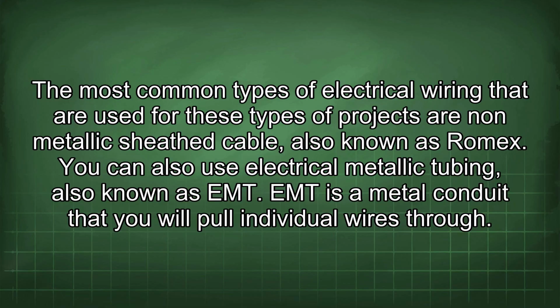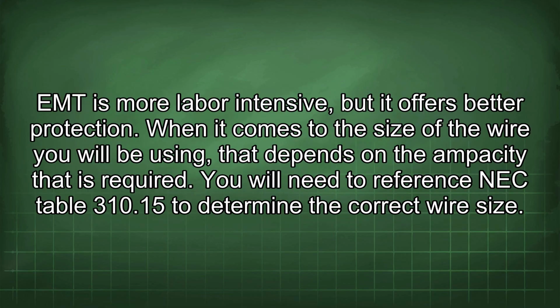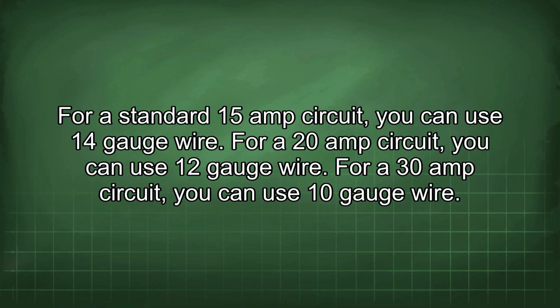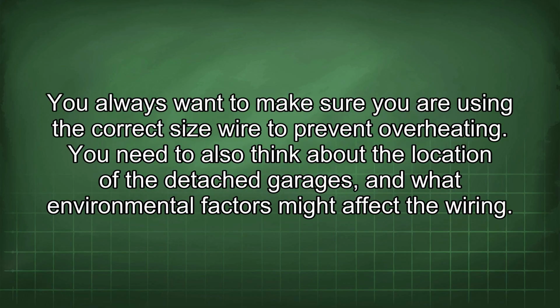EMT is a metal conduit that you will pull individual wires through. EMT is more labor-intensive, but it offers better protection. When it comes to the size of the wire you will be using, that depends on the ampacity that is required. You will need to reference NEC Table 310.15 to determine the correct wire size. For a standard 15 amp circuit, you can use 14 gauge wire. For a 20 amp circuit, you can use 12 gauge wire. For a 30 amp circuit, you can use 10 gauge wire. You always want to make sure you are using the correct size wire to prevent overheating.